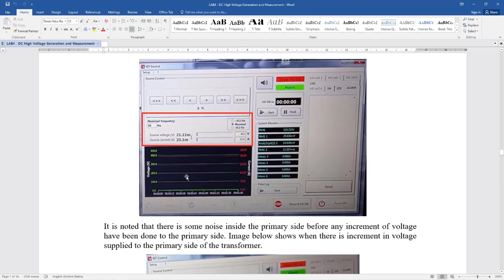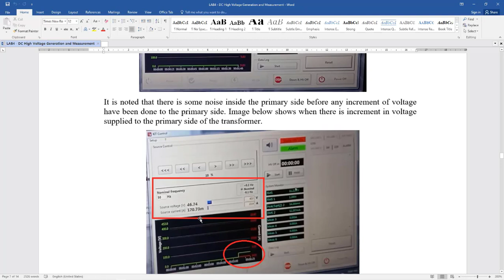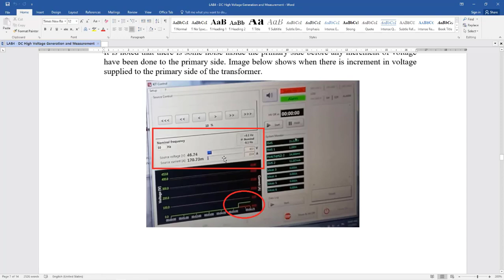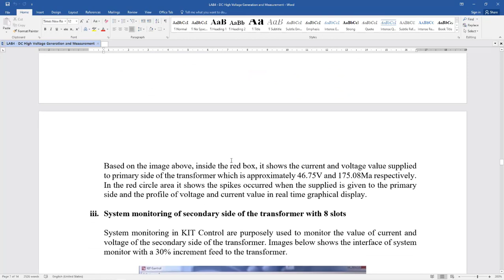Let's say we do an increment of 10% here, clicking the triple button to increase 10% supply to the high voltage input on the primary side. We obtain the source voltage at the primary side right now as 46.74 volts, and the source current as 170.73 milliamps. As you can see below, inside the red circle, we see some spikes, which graphically indicate the increment of source voltage. So both the graphical display and the value here must tally with each other. That is for the primary side.